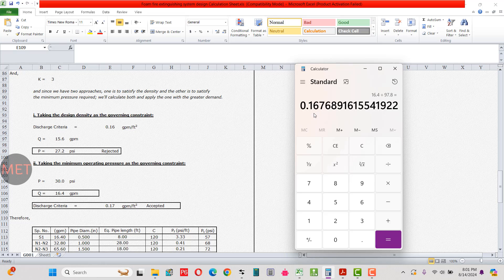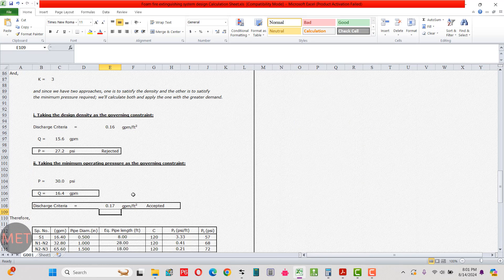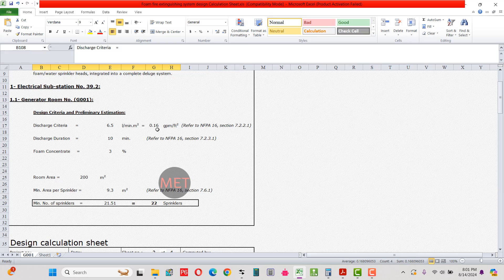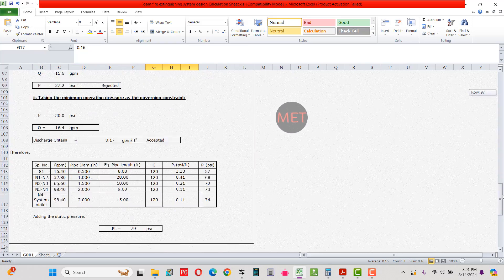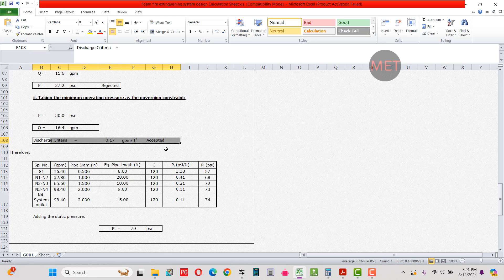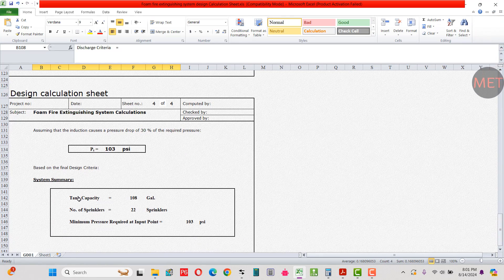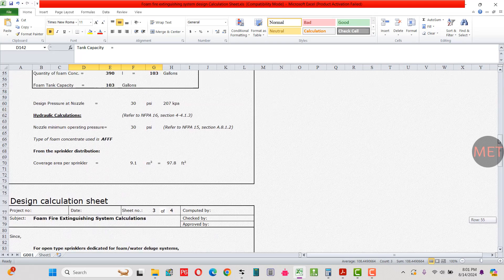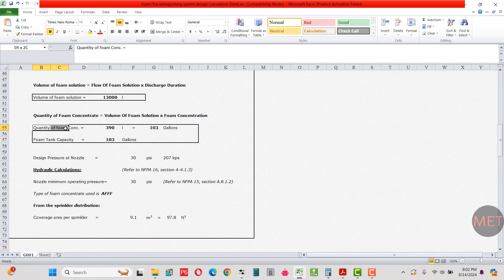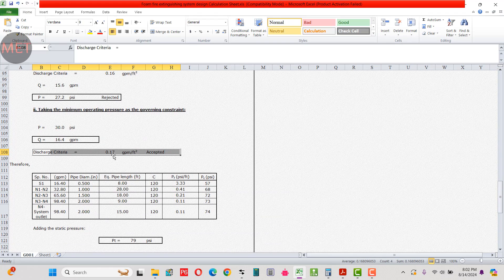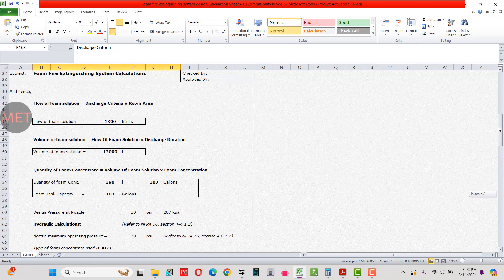Returning to the tank capacity: the initial calculation used 0.16 GPM per square foot, but now we have the actual discharge density of 0.17 GPM per square foot. Using 0.17 instead of 0.16 in the tank capacity calculation gives us the actual foam tank capacity of 108 gallons. The number of sprinklers remains 22, and the last parameter to calculate is the minimum pressure required at the input point.